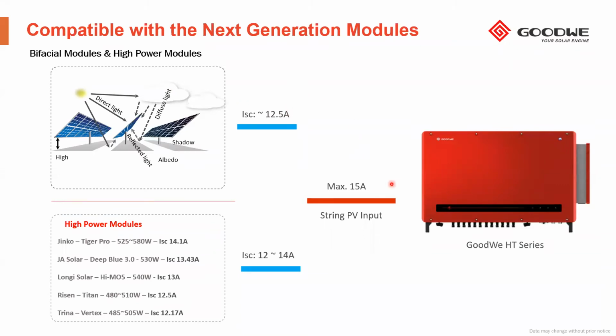And here the relevant thing is that our portfolio, as I mentioned before in the resume, can operate with these new generation modules. And let me open a bracket here. All the inverters, generally the market, could eventually operate high power modules and bifacial modules, right? No matter what they say in the label. The point is that the inverter will cut the input. That means that it will use the available current depending on the design of the inverter, right? What means that an inverter that is not equipped with the proper components will get only the maximum capacity of the inverter per string, not the maximum capacity that the PV string could provide.